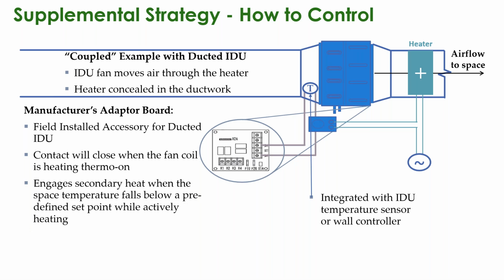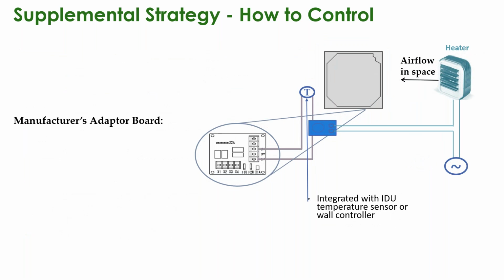It's integrated with the indoor temperature sensor or the wall controller, and depending on the manufacturer, it will switch on based off of a predetermined or preset temperature when the space falls below that point when actively heating. Also ends up referred to as trim heat, if you will. Now, not every variable refrigerant system, although it's very popular to use ducted units these days, is like that. That's not always the case.